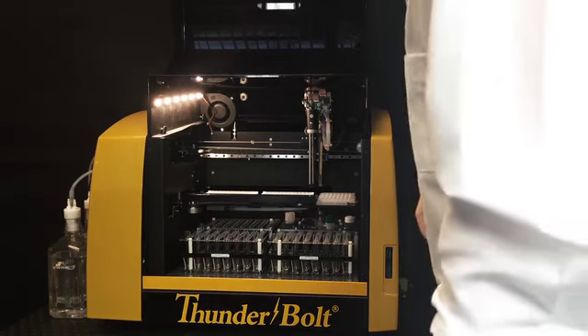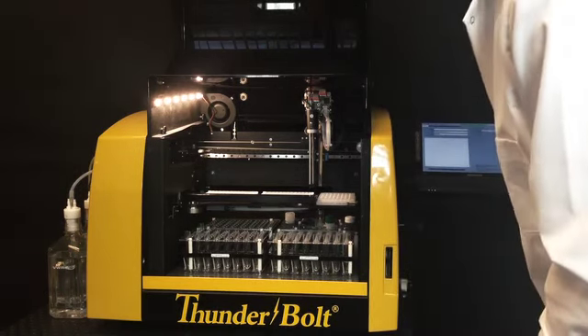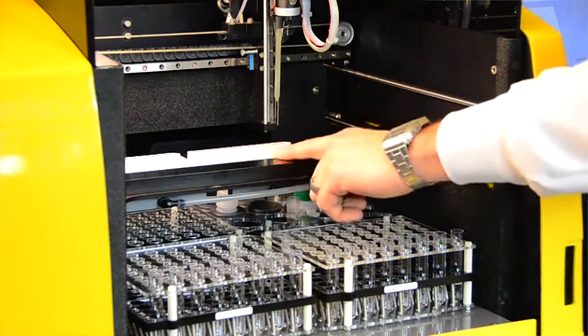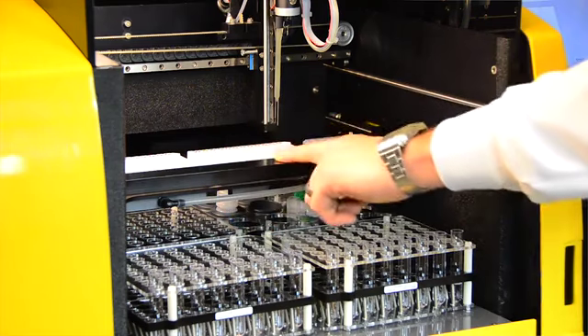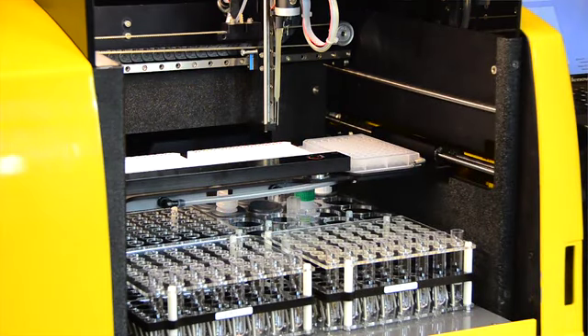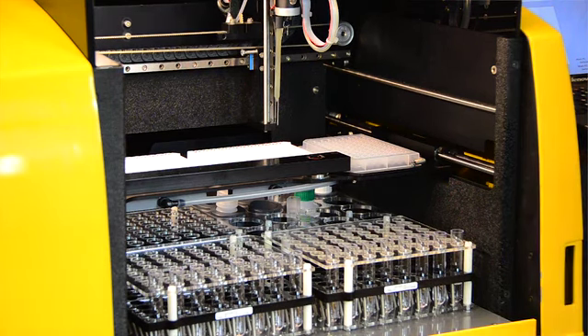This is the Thunderbolt. The Thunderbolt is a 2-plate EIA processor. As you can see, there are places for 2 96 well plates to be placed on the instrument, as well as an extra pre-dilution plate if needed. You will see in a little bit why we are able to run many different tests that require large dilutions and pipette directly into the wells, and therefore do not need the pre-dilution plate.